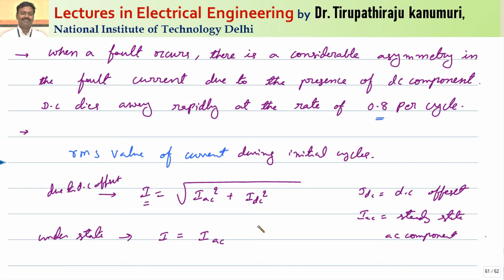Because of this your current is changed. Actually the I_RMS value should be equal to I_AC, but it is now changed from I_AC to square root of I_AC square plus I_DC square. This is due to DC offset. Now under steady state conditions, whatever analysis we have made till now, the current will be equal to the AC component only, because the DC component will die out under steady state conditions. So let us see the impedance seen by the relay under these transient conditions.